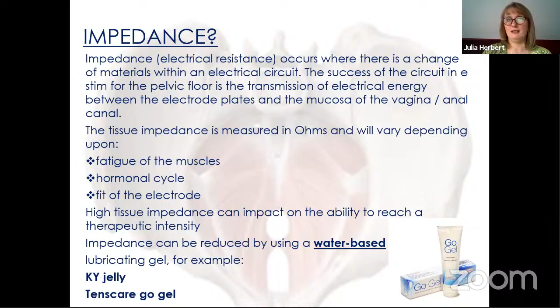You can see there's ones with electrode plates that run down the electrode and ones that run round in a circle. You're actually just trying to make a positive and a negative contact into those muscles. With the ones that run down the plates, there is a directional flow, so it will come out of one side and round to the other, depending which way round you've plugged your leads in. With the circular ones, it will come out of one electrode ring and be collected by the other one, so you're making a circuit in a different way.